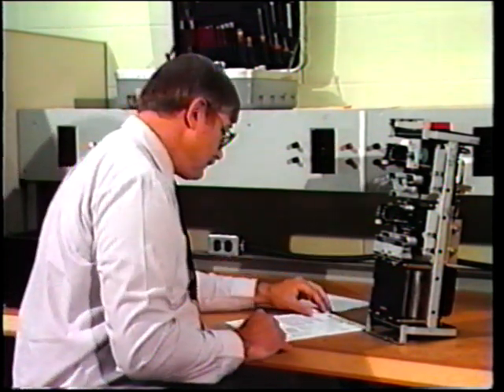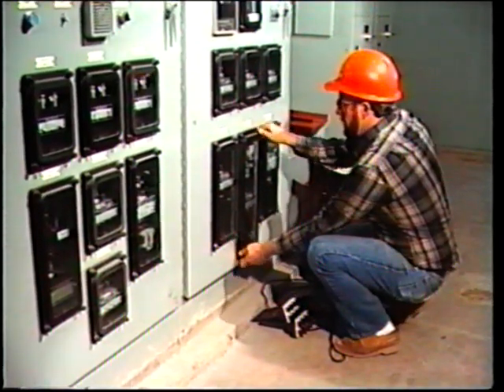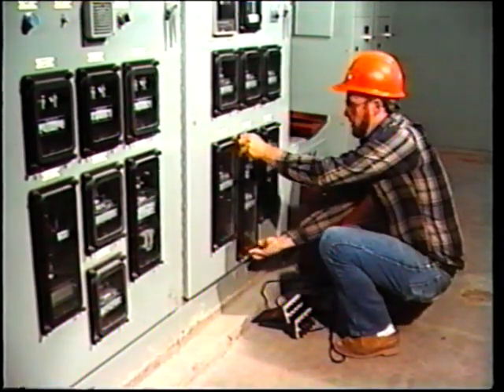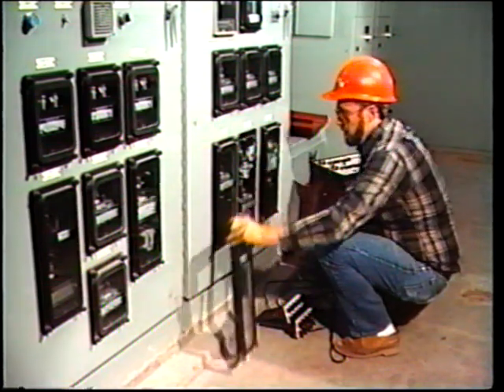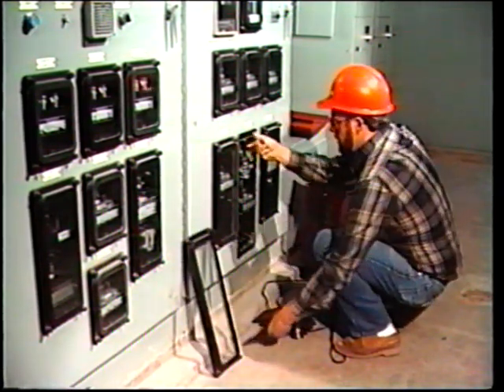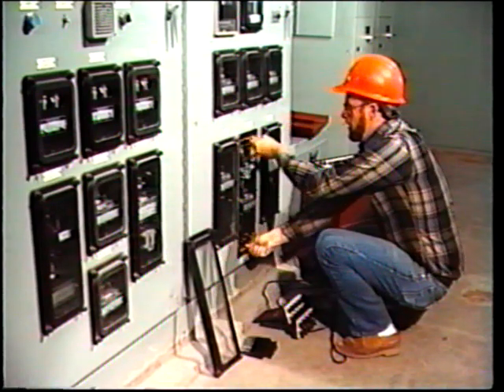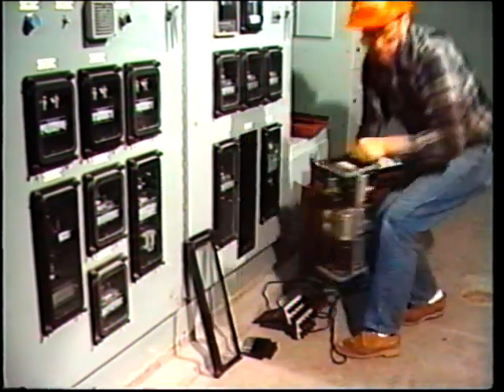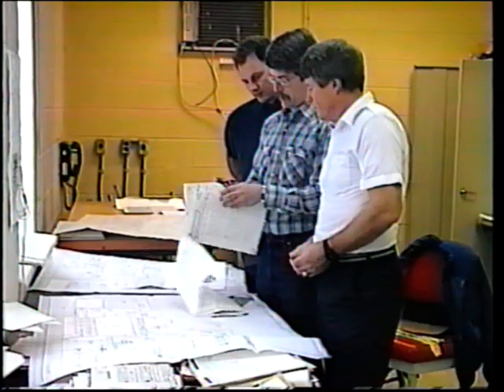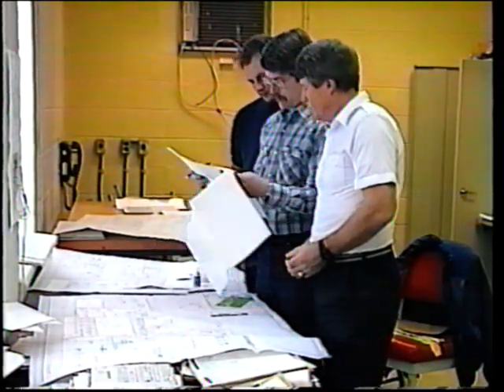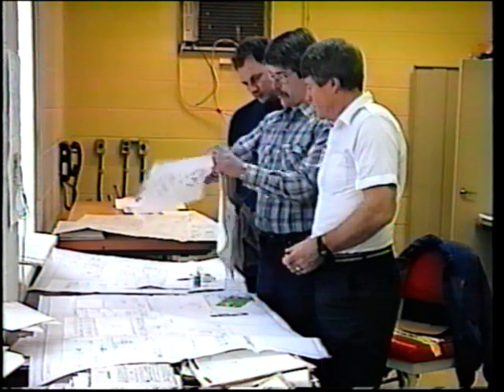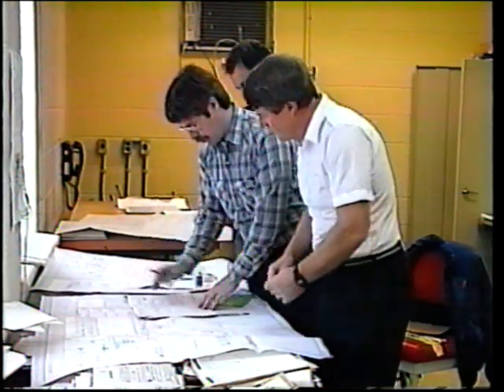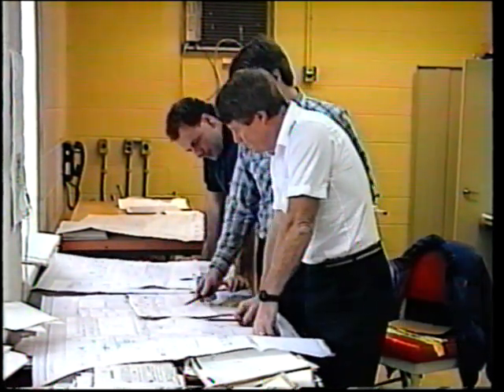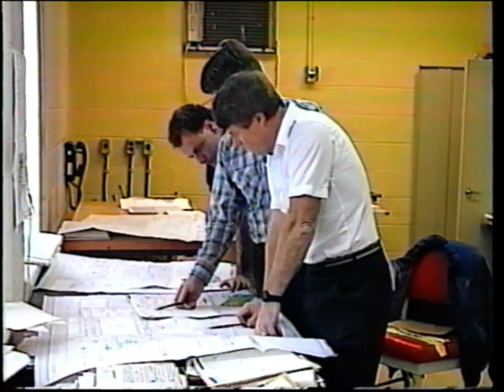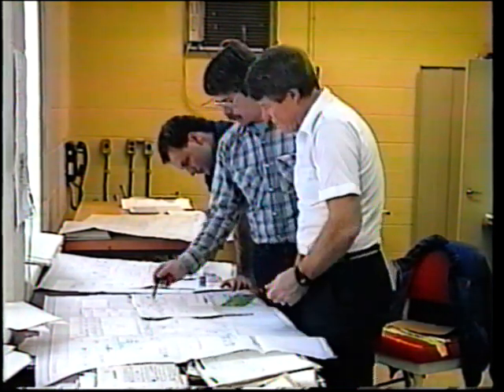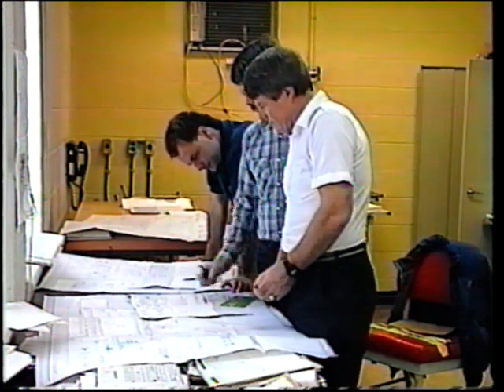specific equipment. While checking the installation, a visual and mechanical inspection should be made of every item of equipment. This means looking out for loose parts, loose connections, shorted terminal lugs, broken glass, foreign material, and so on. Having completed the mechanical inspection, complete electrical tests must be carried out. As preparation for this, we should already have checked that the wiring diagrams conform to the schematics. This can often save us a lot of time in tracking down problems later.